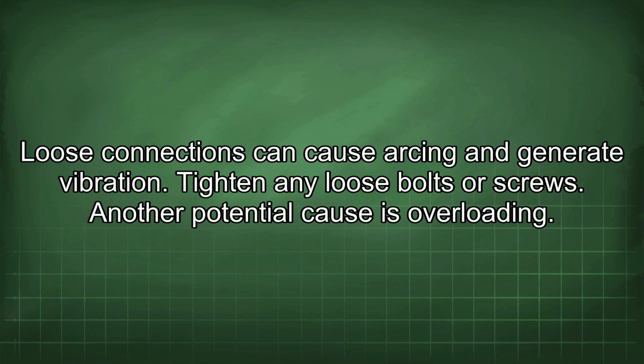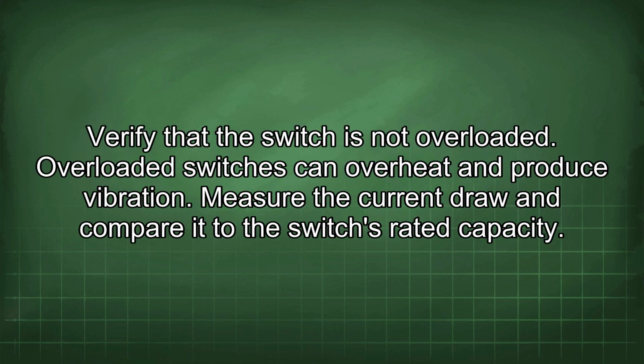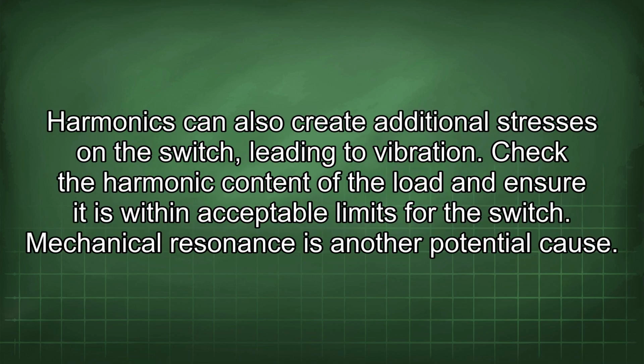Another potential cause is overloading. Verify that the switch is not overloaded. Overloaded switches can overheat and produce vibration. Measure the current draw and compare it to the switch's rated capacity. Harmonics can also create additional stresses on the switch, leading to vibration. Check the harmonic content of the load and ensure it is within acceptable limits for the switch.